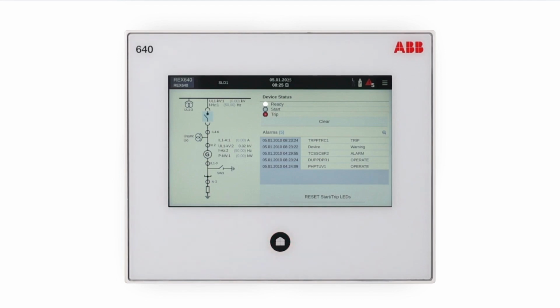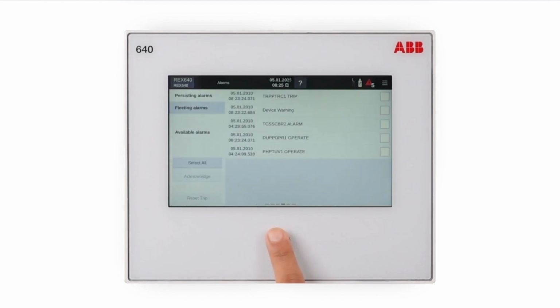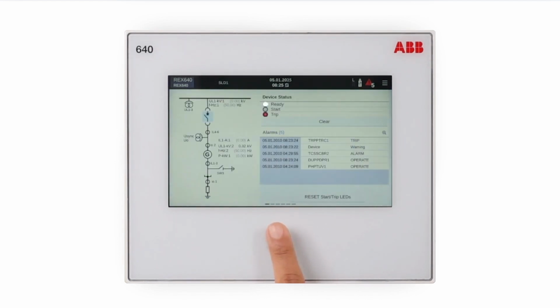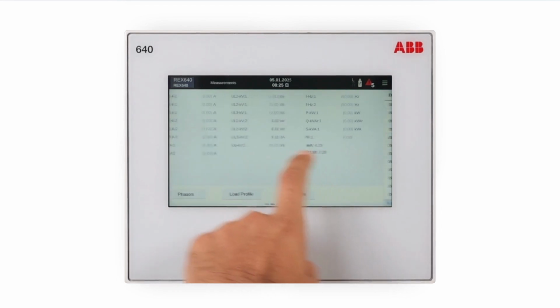The LHMI is used for setting, monitoring, and controlling the protection relay and the related process. It comprises a 7-inch color screen with capacitive touch sensing and a home button at the bottom of the LHMI. The LHMI presents pages in two categories: operator pages and engineer pages. Operator pages are typically required as a part of an operator's normal activities, such as a single-line diagram, controls, measurements, events, or alarms. The operator pages can be scrolled either by pressing the home button or by swiping the actual pages.